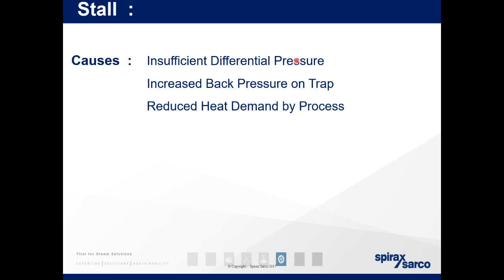The back pressure on traps refers to, effectively, if you see a higher outlet pressure than inlet pressure, you're going to get stall. On a heat exchanger, again, because it's very easy to demonstrate, when you have a control valve to control temperature, sat on the inlet just before the heat exchanger, it will modulate with the temperature. So it will control the temperature by opening and closing. As it closes completely, when it reaches temperature, the steam after it will collapse and create a vacuum. And that can cause stall, because then the inlet pressure is lower than the outlet pressure. So it backfeeds the water into your heat exchanger. Ways we can get rid of that are by pump traps, and other means, which I will cover shortly.